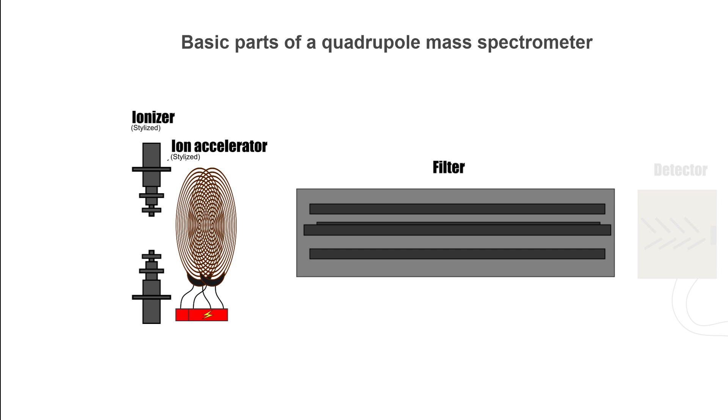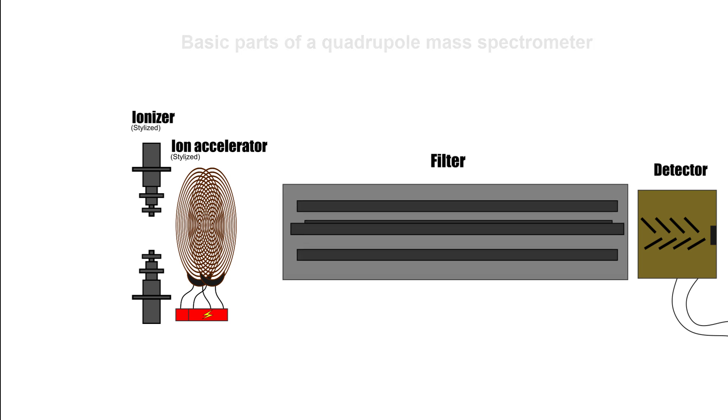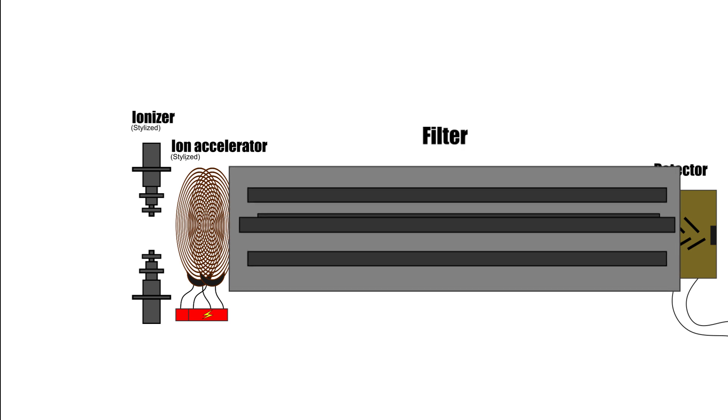In some instances, the ionization process will cause the molecule to fragment to smaller pieces. But in both cases, we now have ionized particles. These particles are then accelerated by an ion accelerator and introduced into the mass filter section. After the filter section, they are then detected by an ion detector. But let's go back to the filter section because this is where things get a little complicated. And this is where you'll also see the technical brilliance of the quadrupole mass spectrometer.